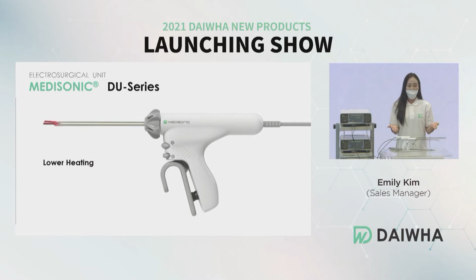Also, Medisonic DU series generates lower heat on the tip. As a result, it minimizes carbonization of surrounding tissues. Since it is ultrasonic energy device, it cuts the tissue right after coagulation through the ultrasonic vibration. If you select high mode, you can coagulate and cut almost at the same time in about 3 seconds.